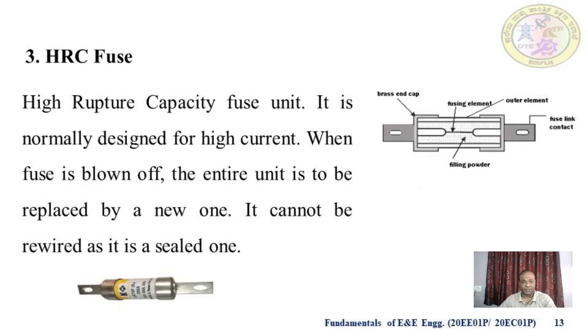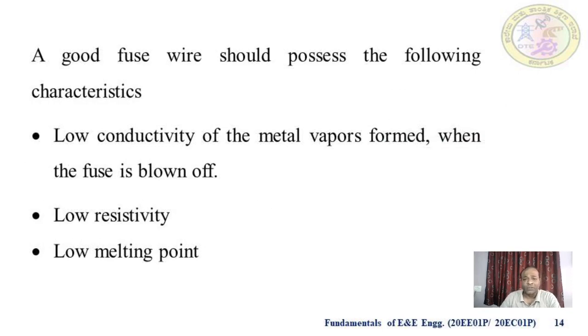The HRC fuse, or High Rupturing Capacity fuse, is normally designed for high current. When the fuse is blown off, the entire unit must be replaced by a new one — it cannot be rewired as it is a sealed unit. A good fuse wire should possess the following characteristics: low conductivity of metal vapors formed when the fuse is blown off, low resistivity, and low melting point.